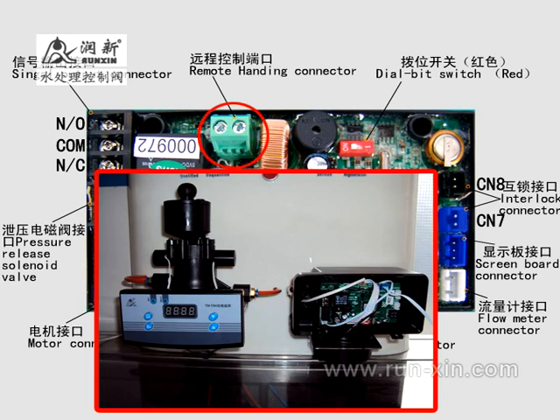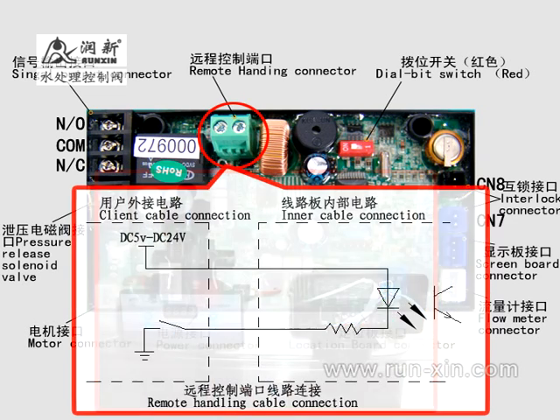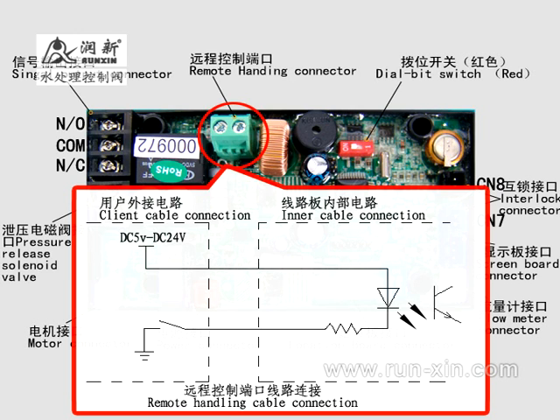Remote handling connector. This is used when the valve is used for making pure water, or in an online monitor system, or connected with a PC device. When electronic conductivity or another parameter arrives at a set value, or the PC sends a signal, the system needs to regenerate. The signal would be sent to the remote handling connector on the main control board to force the system to start regeneration.